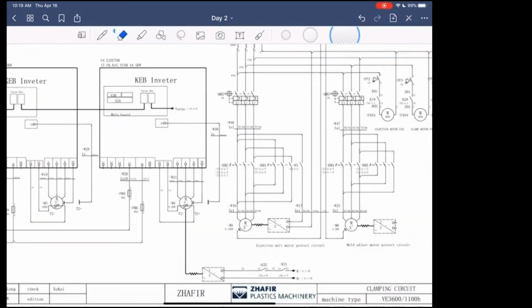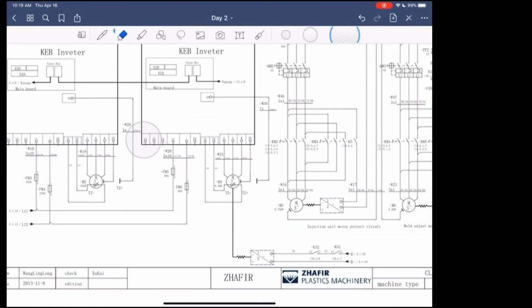All right, again, it's the same thing, except no line 1, line 2, line 3. All you have is the DC bus being fed to the drives. So what the drive does after it gets this DC signal, it then converts it to an AC frequency. I believe the frequencies are up to 1,000 hertz.